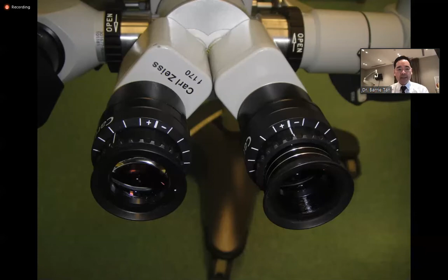So the first problem is that the zeroing of this particular lens is not at the 0 mark. So here, in terms of the operating lens and operating microscope, you are able to correct for any of your own myopia, and you can correct it using the plus and minus function and rotating the dials. And so if you're able to zero it, and if you wish to still operate with your own spectacles, then you should ensure that the entire eyepiece is zeroed, both for the lens as well as the reference 0 mark.